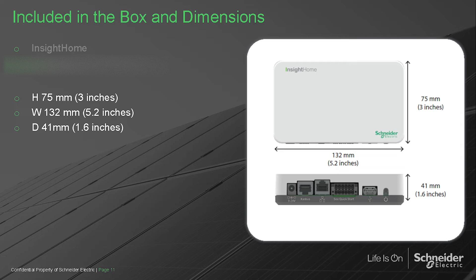The USB port is used for firmware updates. You can also use USB for discovering the IP address via DHCP when hardwired to your router. The 12-pin port allows you to provide power to InsightHome as an alternate source other than AC adapter or Xanbus. It also provides a single CAN bus network connection, a single RS-485 connection, and 2 inputs for features that are on the roadmap. The Ethernet port is used to connect to your router, and the Xanbus port is used for Xanbus communications.